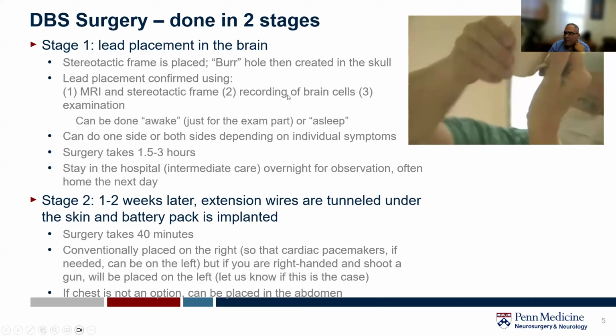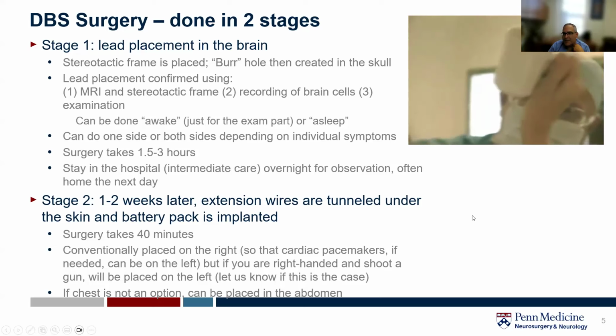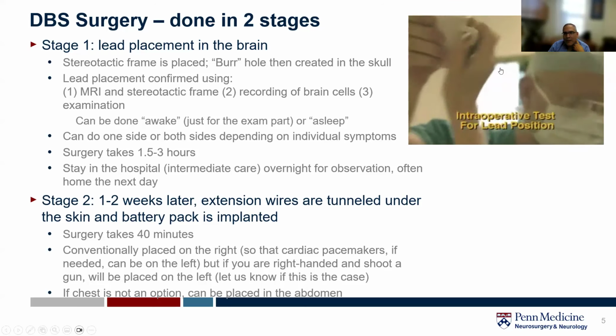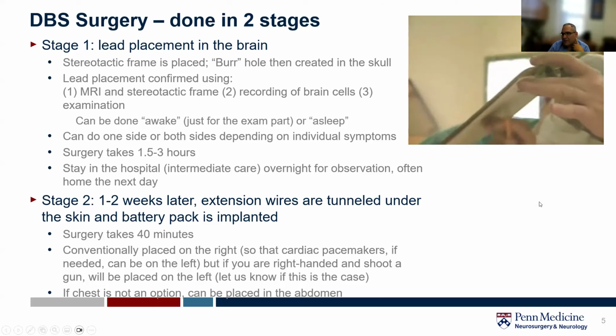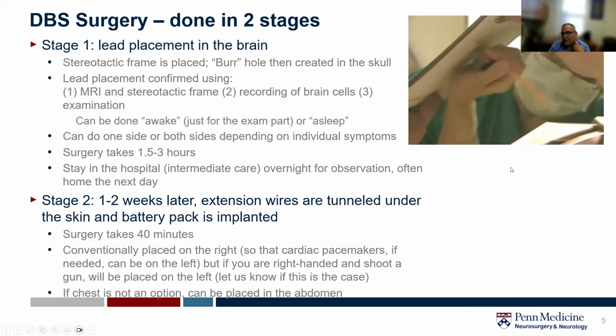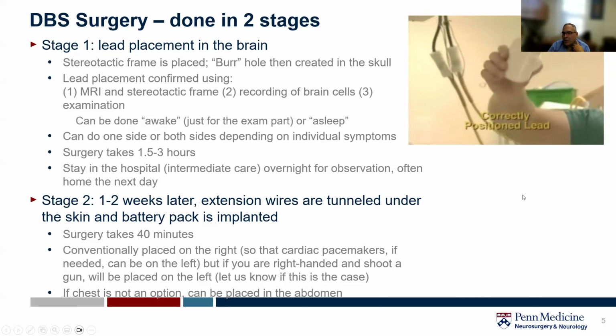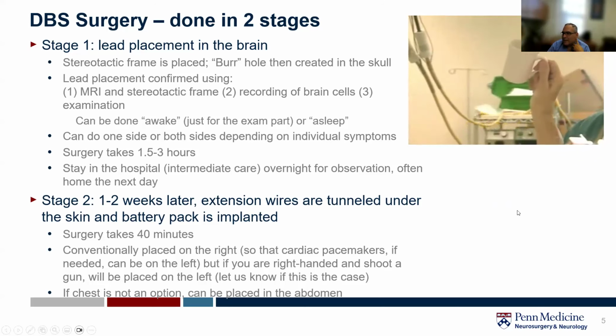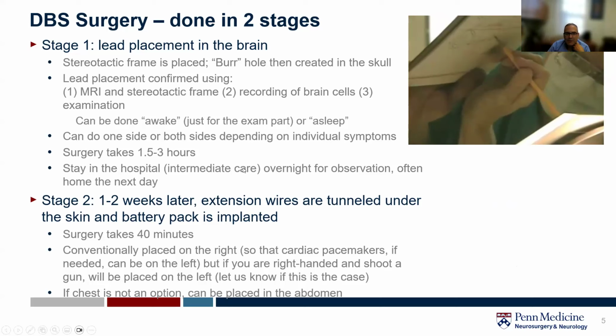And then lastly, we tend to use awake testing to make sure that the stimulation not only is helpful for the tremor, but that there are no side effects to the stimulation. The benefit of this is if there are any side effects, we can reposition the electrode with millimeter accuracy to a new spot that will have the same improvement in the tremor and the lack of side effects. On the top here, you can see an example of the type of testing we might do in the OR. We don't bring in glass cups here at Penn. This is an older video, but we might do things like intraoperative spirals like this, just so that we can compare once the stimulation is turned on, that the tremor actually gets better and that the spirals improve.